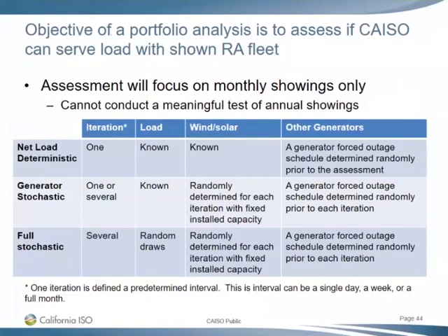We've got a local model right now where we conduct studies and we can put you in a general understanding without setting horrifically complicated local RA requirements where we have to count each resource for every local area, sub-area, and constraint that it's addressing. We have this effectiveness factor that does a pretty good job, but it's not perfect. In some ways, it can be off depending on whether the first contingency is on the east or the west. So we've made simplifications in local, and we've got to a place where people generally understand what the profile within a local area looks like, what our local needs look like. And I can look at effectiveness factors and know how well I'm doing and what the risks of backstop costs are.